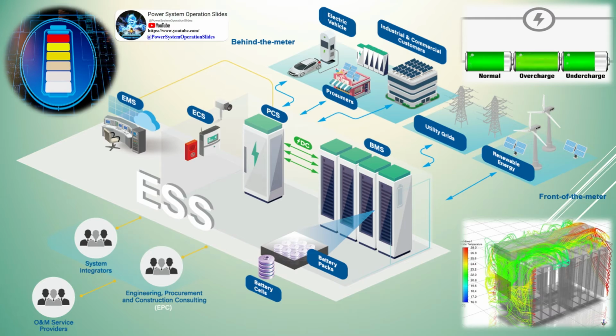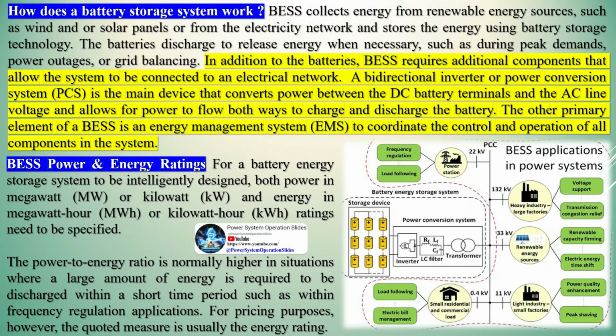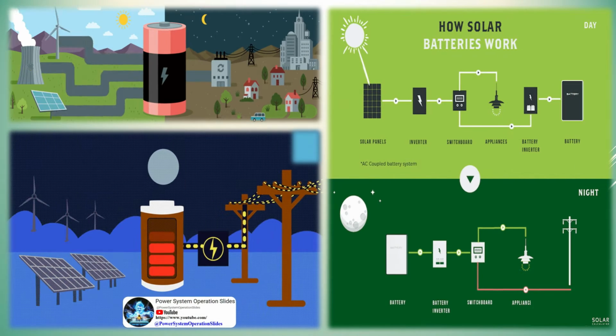BESS power and energy ratings. For a battery energy storage system to be intelligently designed, both power in megawatt (MW) or kilowatt (kW) and energy in megawatt-hour (MWh) or kilowatt-hour ratings need to be specified. The power to energy ratio is normally higher in situations where a large amount of energy is required to be discharged within a short time period, such as within frequency regulation applications. For pricing purposes, however, the quoted measure is usually the energy rating.